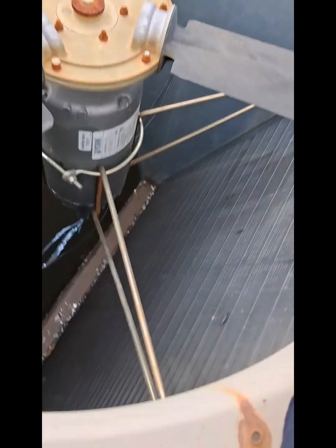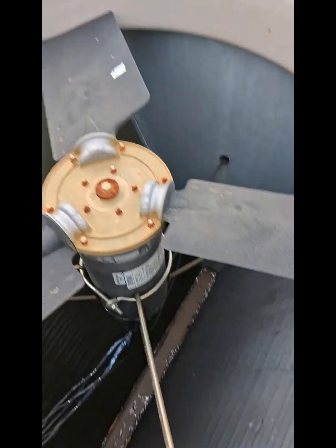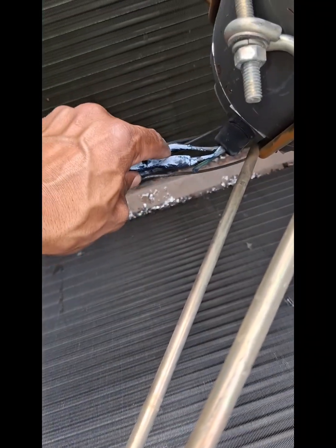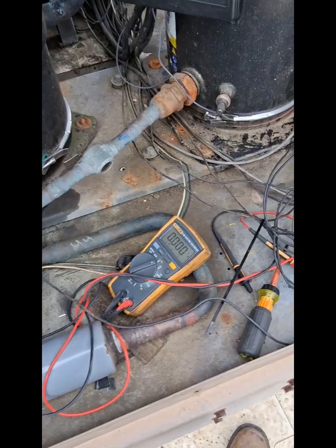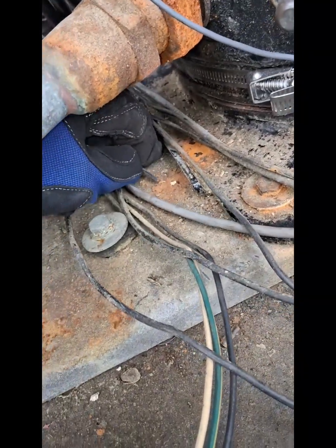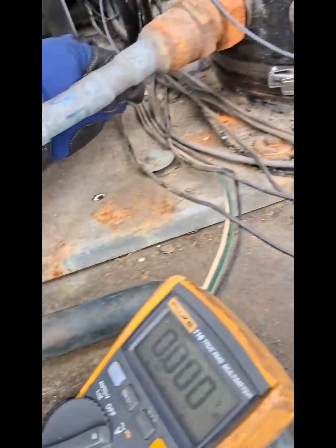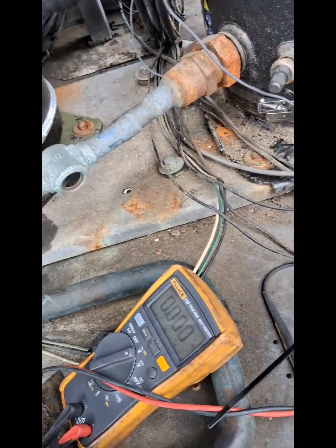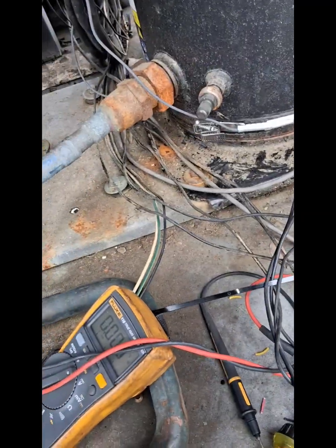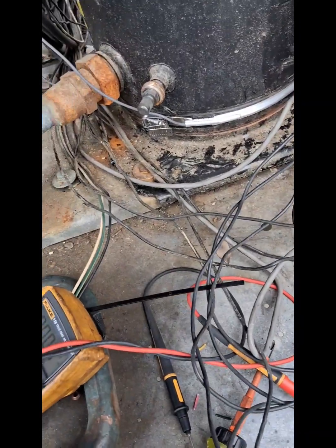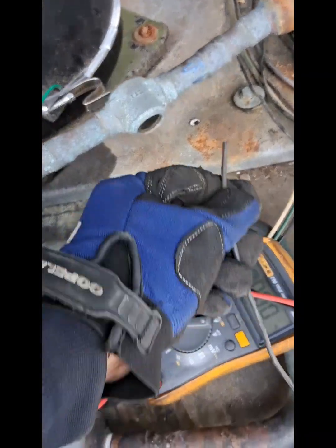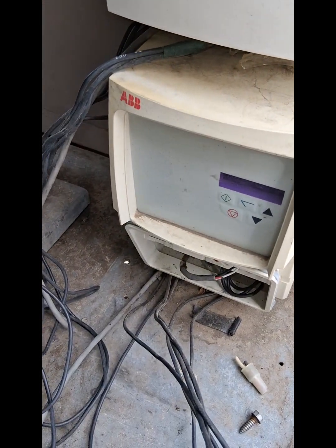Circuit 2 running. I got voltage going leaving the contactor coming to this fan, but it's not coming on. And I think the problem is that right there, it's hard. So I gotta strip this, make some new wire connections, and the fan should come up and run. Well, I found the real problem. This wire right here next to my drive, which wire is it? It's a cut wire here somewhere. It's one of these 3 wires. It's cut. This one. That's gotta go right there. And the F001 alarm will come off and my fan should start up.